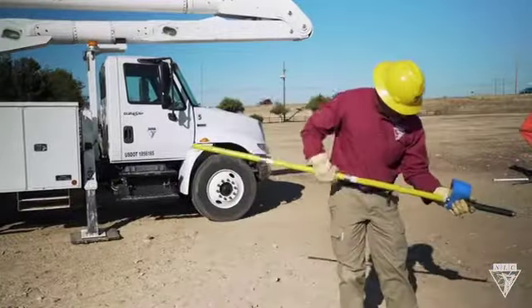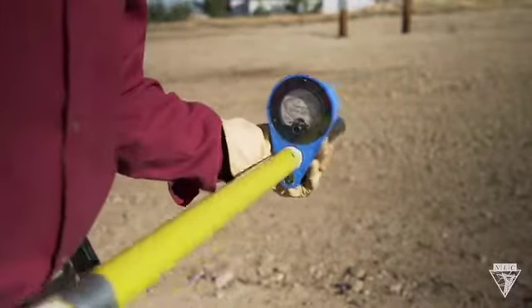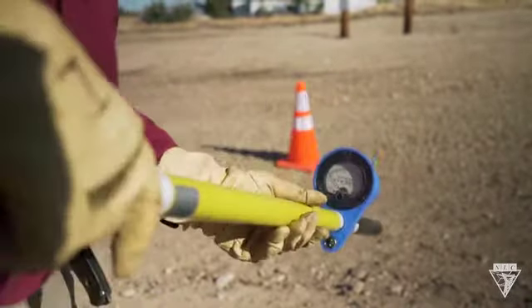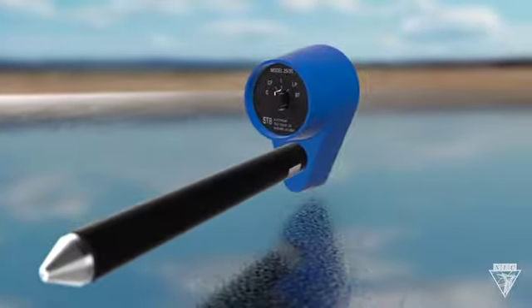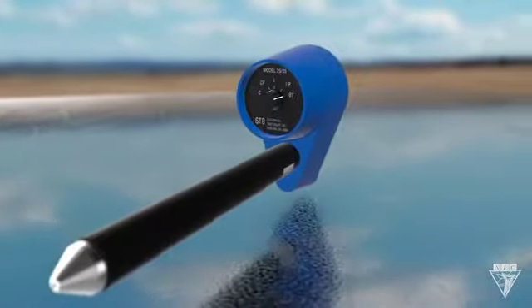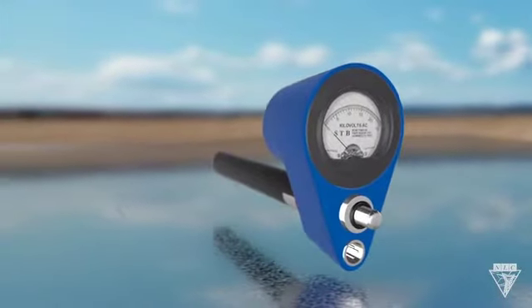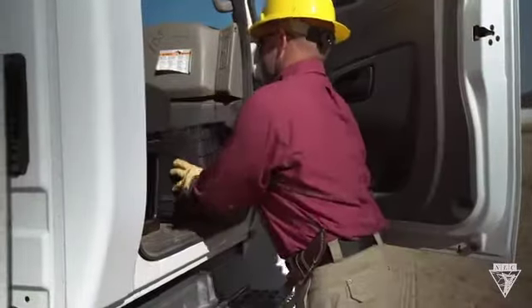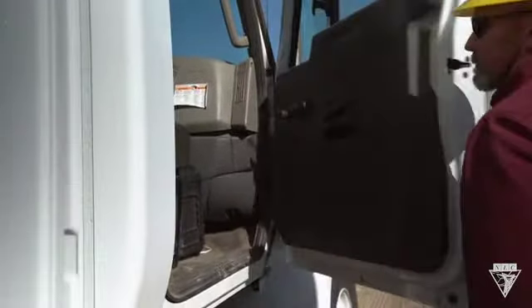Before using the meter, you should always perform 2 tests: the battery test and the proof test. To check the battery, turn the dial to BT. If the needle doesn't deflect, do not attempt to use the meter and remove it from service until the battery is changed and proper operation is verified. If the needle does deflect, it's safe to continue.